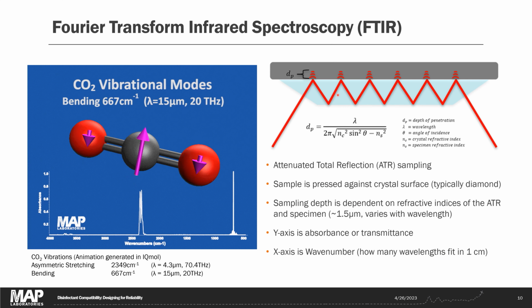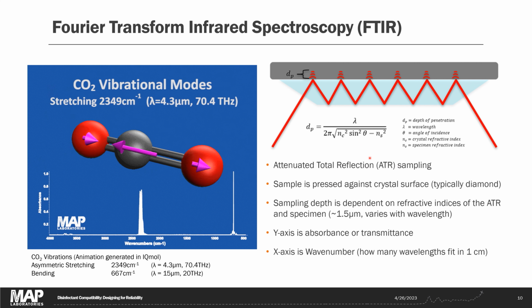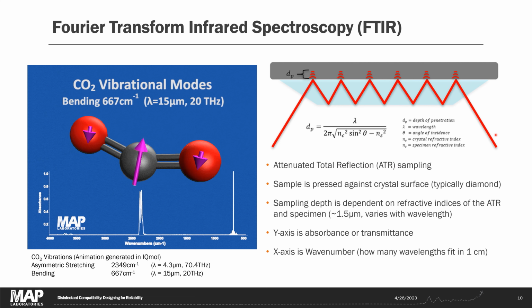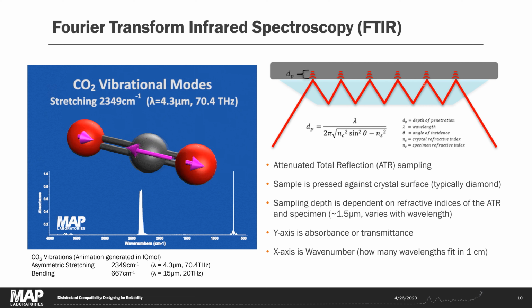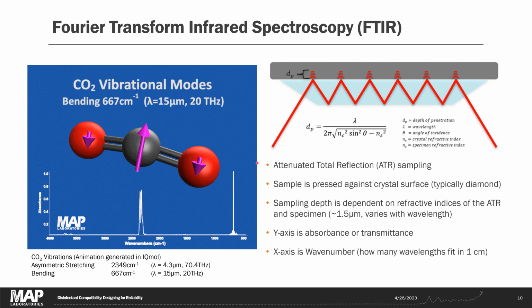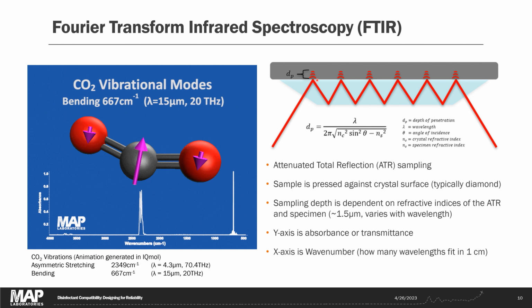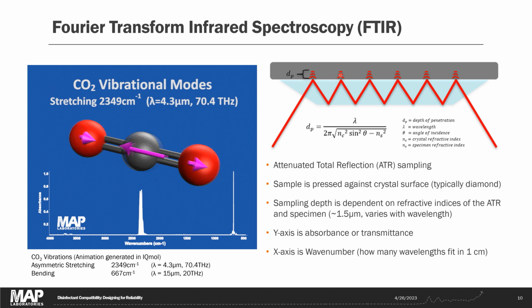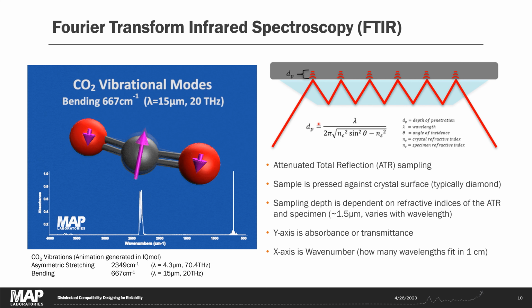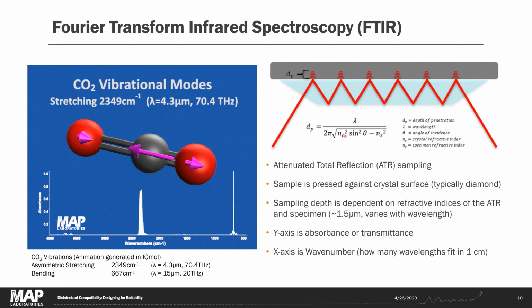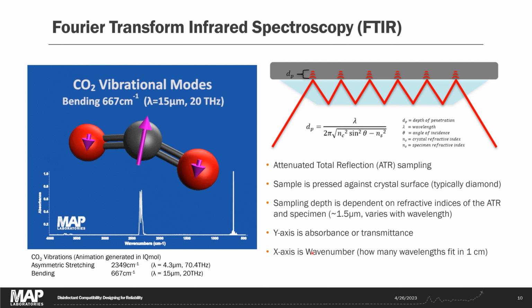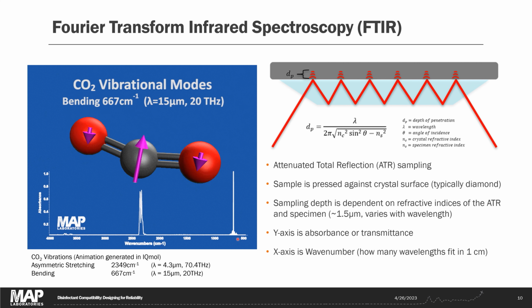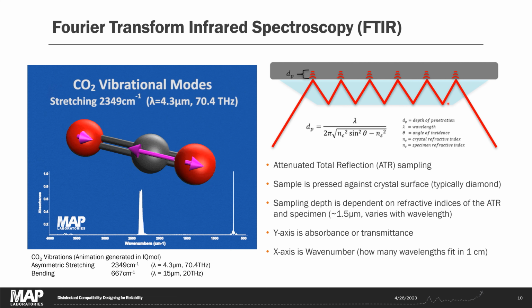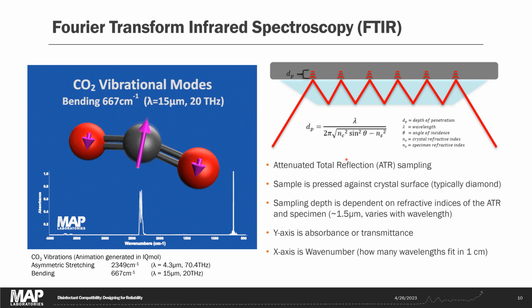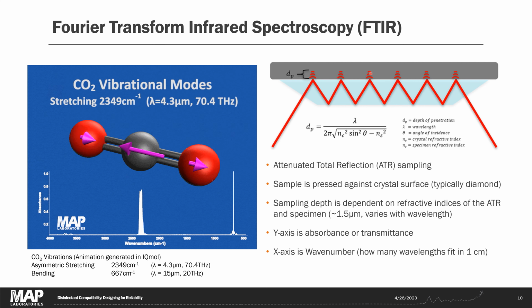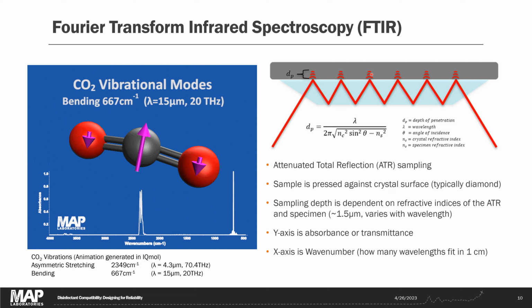Here's a diagram of an attenuated total reflection, or ATR, crystal. The infrared beam comes through the crystal and bounces back and forth by total internal reflection. There's a small evanescent wave that extends into the sample, roughly by this equation here. So we end up with a depth of penetration that's dependent on the wavelength. We're sampling a little bit deeper on this side and a little bit shallower on this side, but roughly a micron or so of penetration into the sample surface. And that's where we're actually measuring the chemical composition.